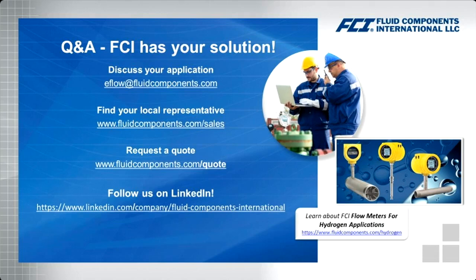That's a great question. So the short answer is yes. They use the same technology from the sensor perspective. The difference is how the electronics paired with that process that data and create a signal. But as far as the sensor itself goes, yes, we use the exact same technology. There is no difference. It's just discrete outputs versus your analog or your digital protocol that you're using to indicate your flow.